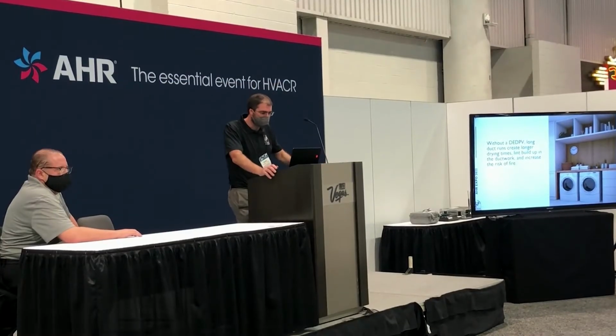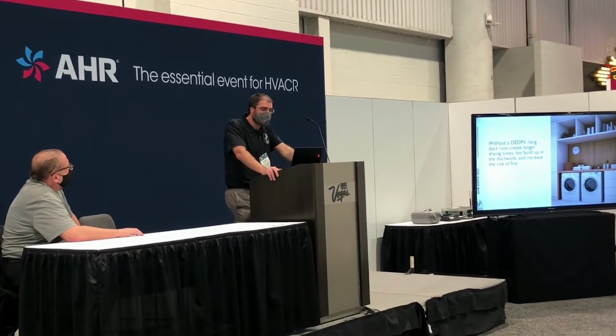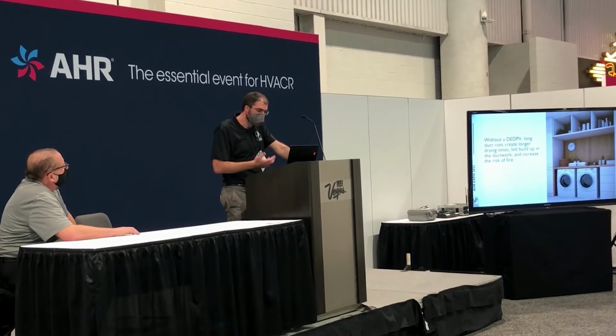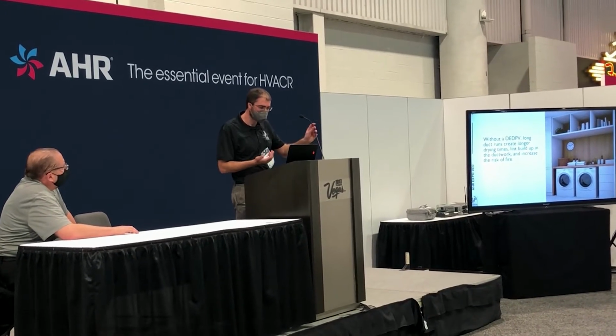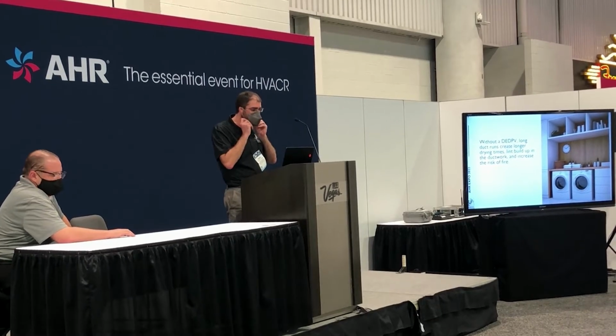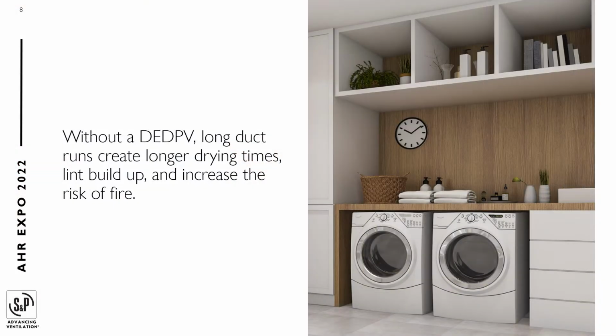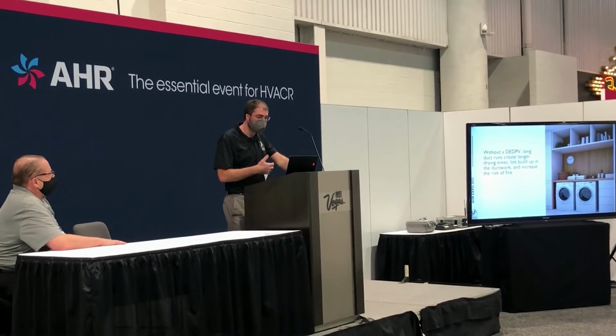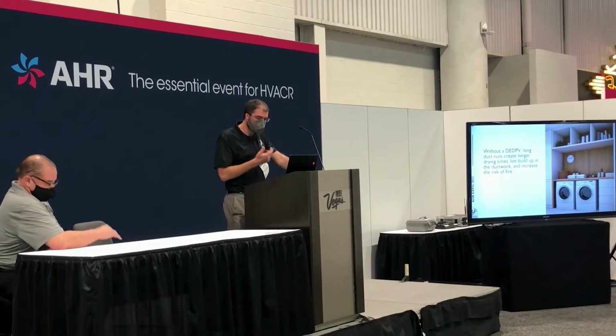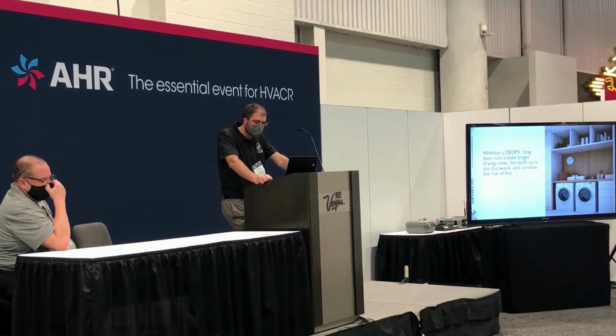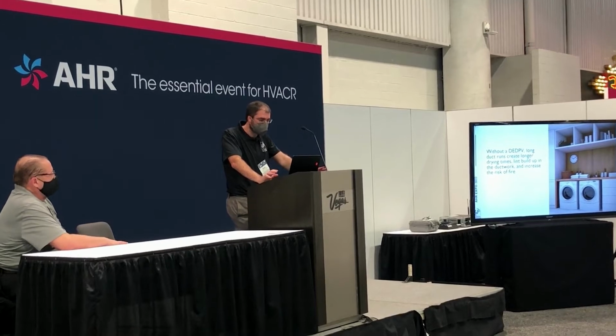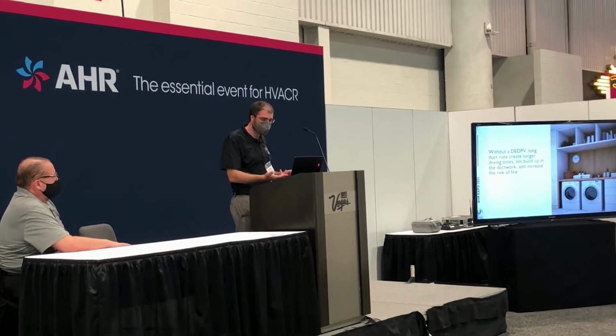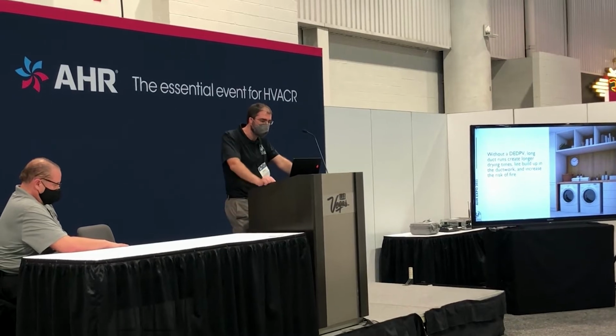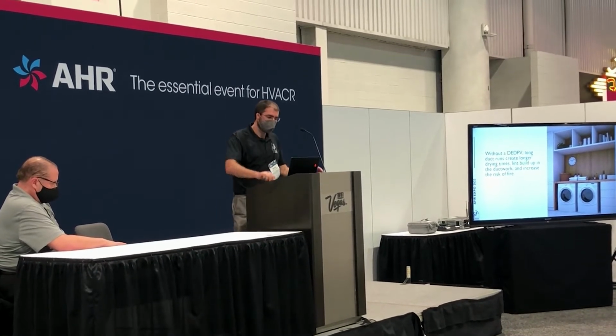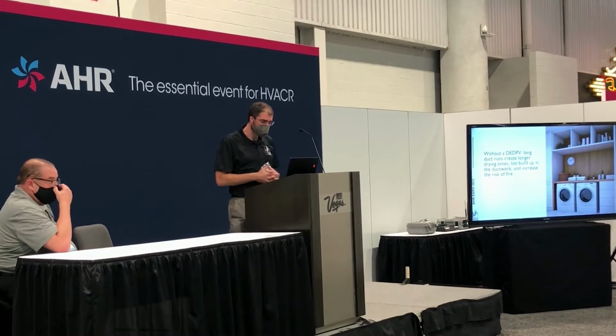So why are long and complex duct runs problematic? They provide increased pressure resistance on the dryer, which can lead to a reduced air velocity throughout the ductwork, which increases the chance of lint buildup along the dryer walls, which subsequently increases the risk of fires. The maximum recommended equivalent length of ductwork by the 2012 through 2021 International Residential Code, or IRC, is 35 feet. And that's just due to these hazards.